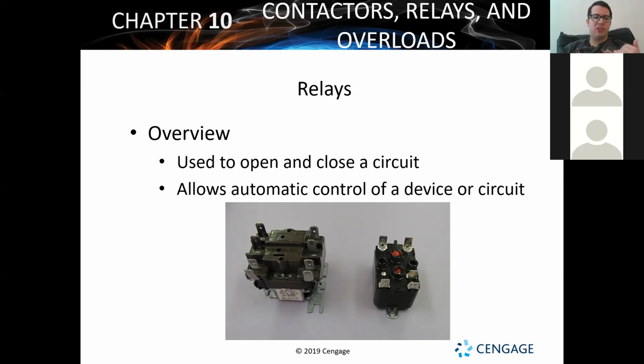Okay, relays are the same exact thing as a contactor. There's nothing different between a relay and a contactor except for one thing: a relay can only handle small loads. Blower motors for residences are one of the most common spots you'll see a relay used. Inducer draft motors for residences are another common spot. Most commercial motors are too large to use a relay on, so you don't see them too often outside of residential.